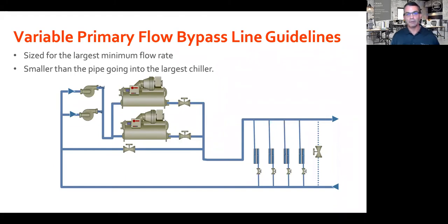Conceptually, a variable primary flow system is simpler to get right. The bypass valve is just below the chillers. And again, sizing that pipe and valve are critical to the operation of the plant. The valve in the bypass line only opens when the system flow rate nears the minimum flow rate of the chiller. So the bypass pipe and valve only need to be sized for the largest minimum flow rate. Usually that's the largest chiller's minimum flow rate, but depending on chiller selections, the largest minimum flow rate could be for a smaller chiller in the plant. It should be smaller than the pipe going into the largest chiller.